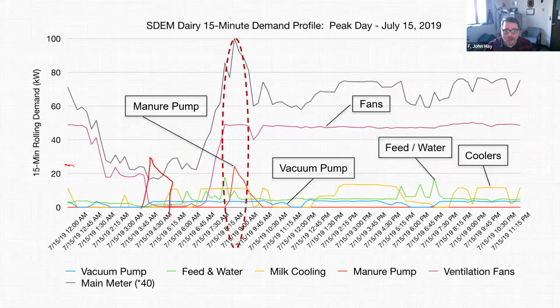Now, this is a great example of where it works perfectly. Your examples may not be as perfect, and your level of data, at least initially, won't be this good. So there could be some trial and error involved. In my case, the peak was set at 8:15 a.m. on July 15th. Thinking about what was happening at my operation at that time, is there anything non-critical that doesn't have to happen then? Can we do some load shifting to reduce that? That starts with making a list of all your loads.